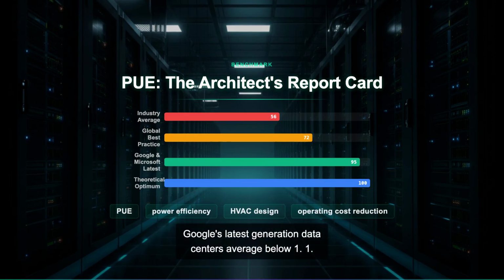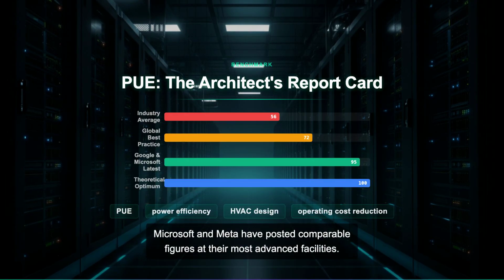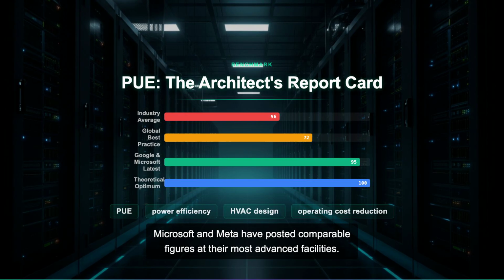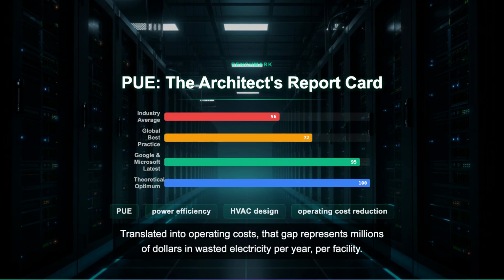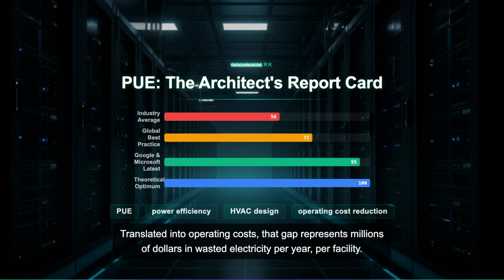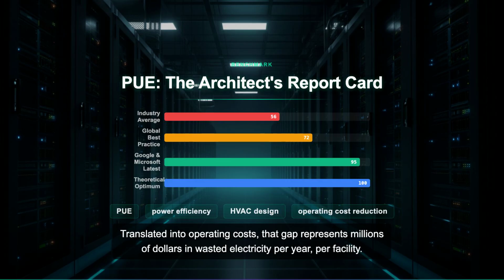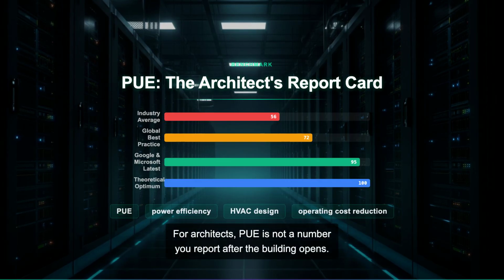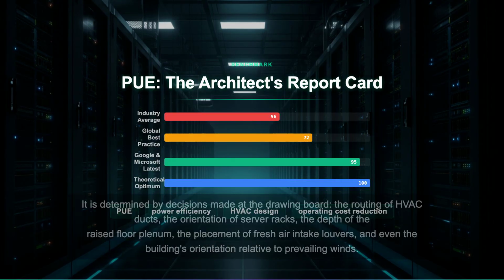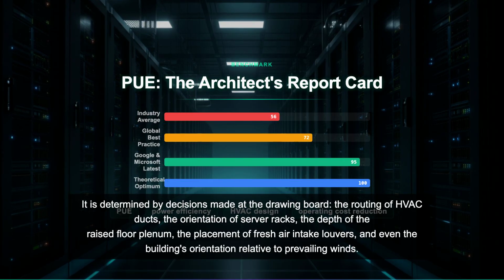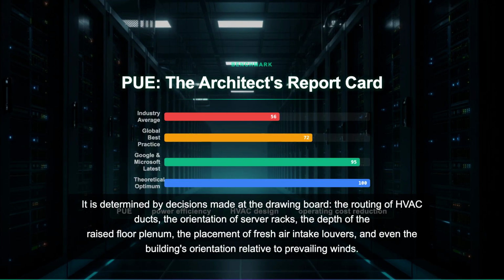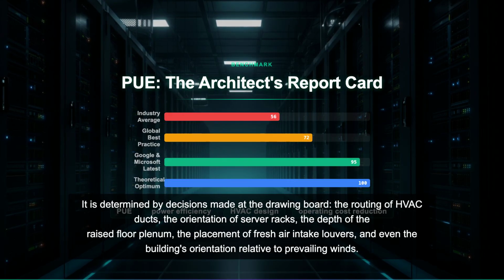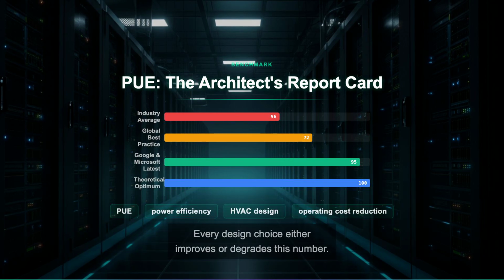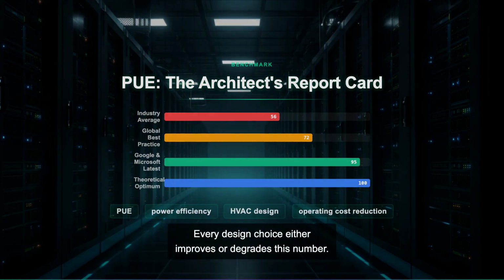Google's latest generation data centers average below 1.1. Microsoft and Meta have posted comparable figures at their most advanced facilities. Translated into operating costs, that gap represents millions of dollars in wasted electricity per year, per facility. For architects, PUE is not a number you report after the building opens. It is determined by decisions made at the drawing board. The routing of HVAC ducts, the orientation of server racks, the depth of the raised floor plenum, the placement of fresh air intake louvers, and even the building's orientation relative to prevailing winds. Every design choice either improves or degrades this number.